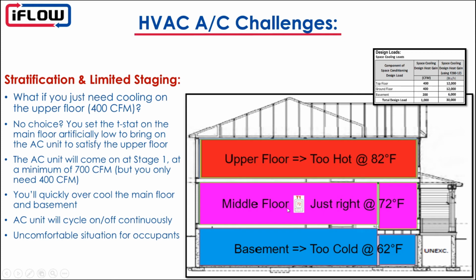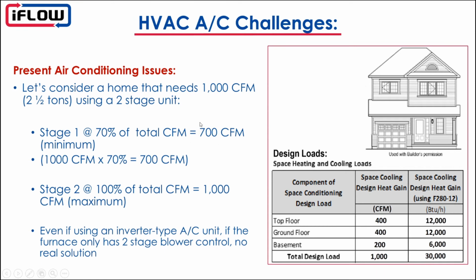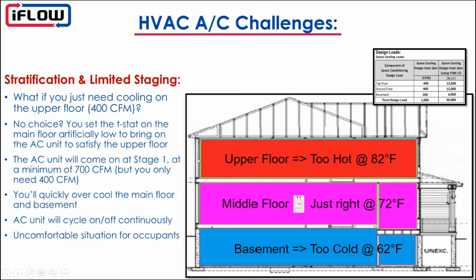So as we saw by this distribution, we only need 400 CFM in the top floor, but as we saw by the staging, minimum delivery is 700 CFM. Okay, so we turn the air conditioning on, but again, the middle floor is already satisfied. So what are we going to do? We're probably going to decrease this artificially. We'll probably drop it down to 65 or 60 to bring the AC unit on to maximum.